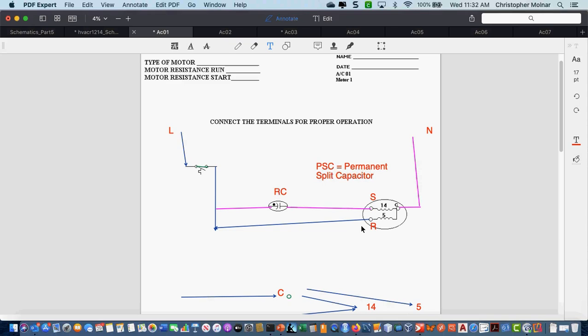PSC motor. Now, in HVAC, our PSC motors have always been traditionally used on blowers, on the indoor fans. Okay, the blowers that are blowing the air through the ductwork. That has been the most traditional use of the PSC motors for years. I caution you, by the time you graduate and get through part of your apprenticeship, we're going to see very few PSC blower motors. So this is changing very fast.